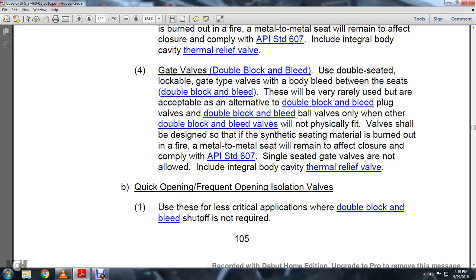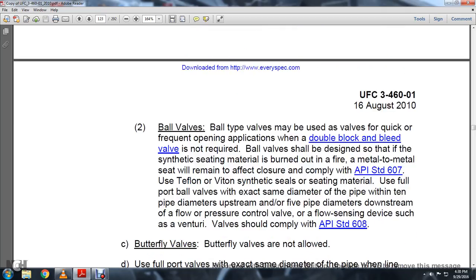B. Quick opening, frequent opening isolation valves. Use these for less critical applications where double block and bleed shutoff is not required. Ball valves, ball type valves may be used. These valves are for quick, frequent opening applications where double block and bleed is not required.